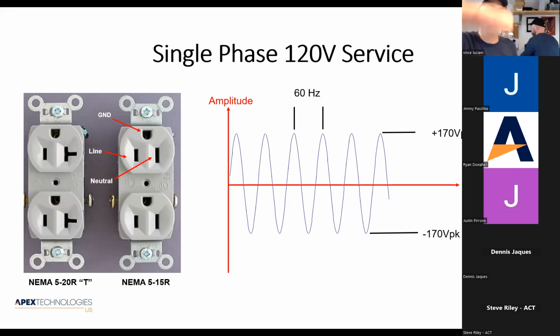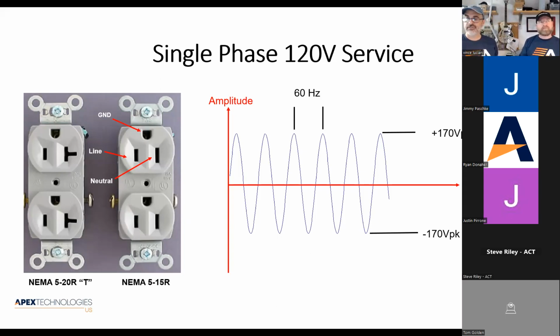So what that does is it prevents that 20 amp load from plugging into a 15 amp outlet, right? Because if you did that, you would blow the breaker, and it would be a pain in the butt. Couldn't we just chop it off and make our own? You could, but that would be wrong, because you would be putting a 20 amp load on a 15 amp circuit. That's not good, unless you want to rig up a way to turn the breaker on all the time.